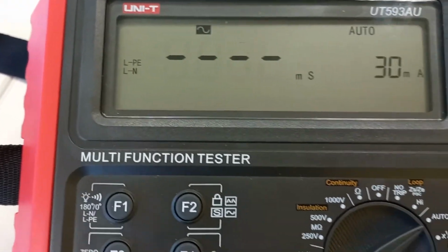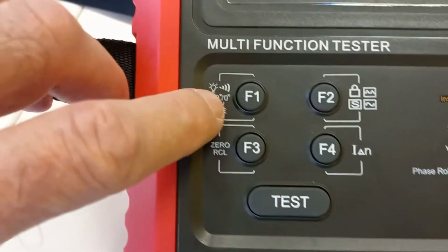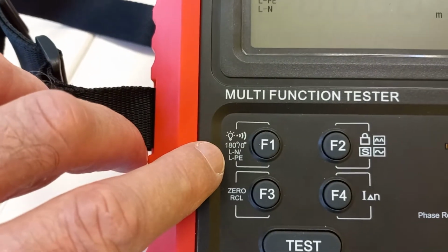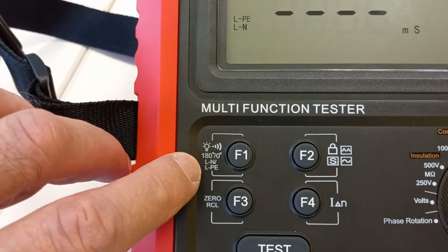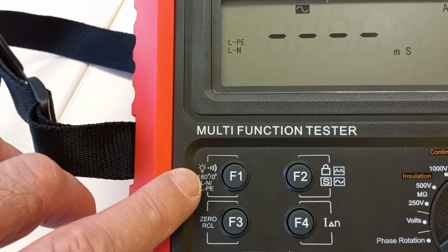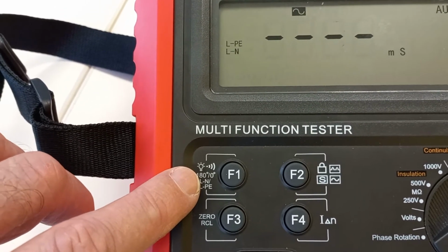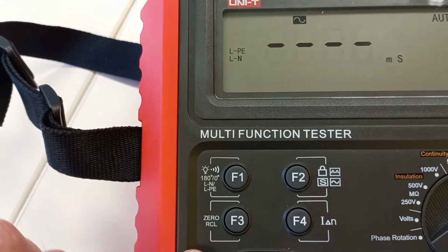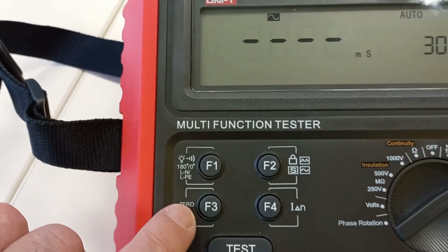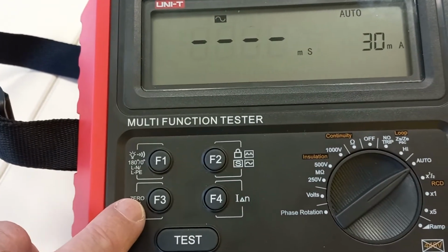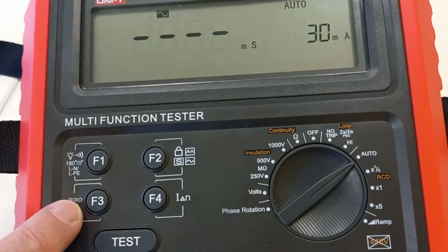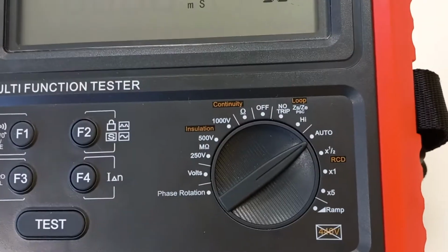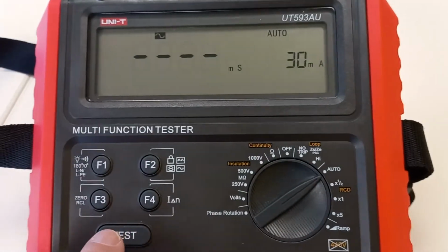Also, the setting allows for 0 and 180, so I can start my test at the beginning of the cycle, or at the beginning of the negative half of the cycle. This recall here, F3, is where we pull back the results after the auto function is carried out. So we're in auto function now. I'm going to press the test button.